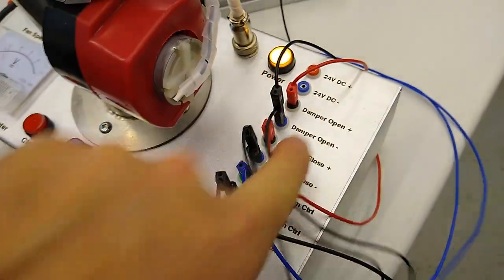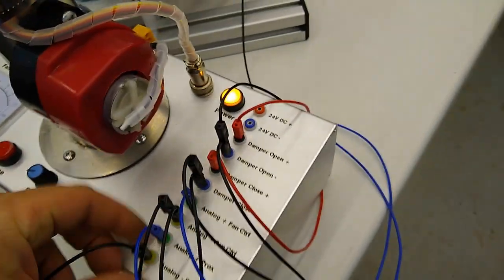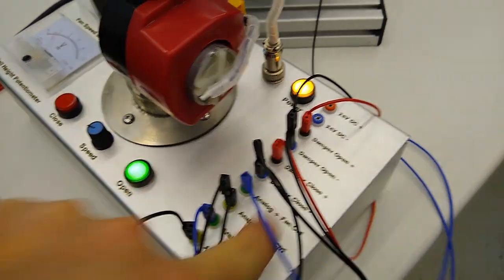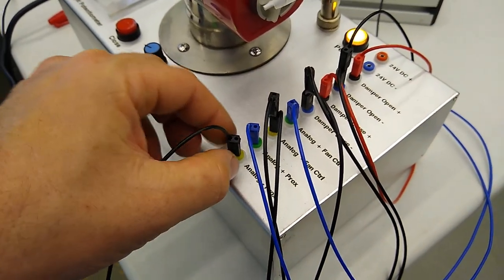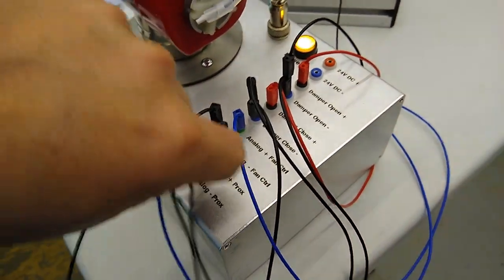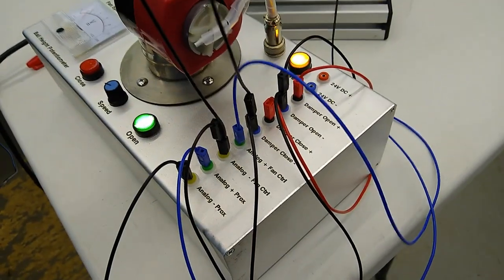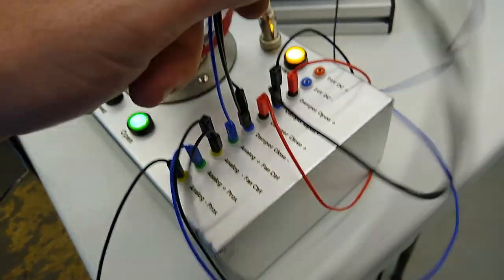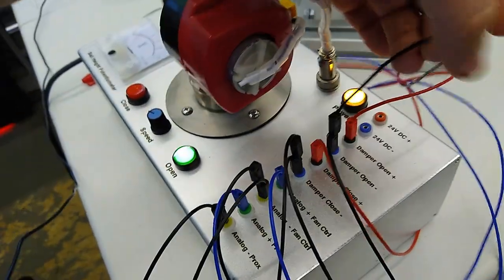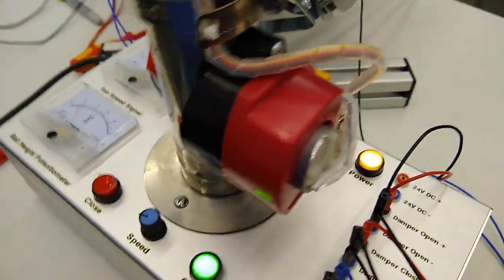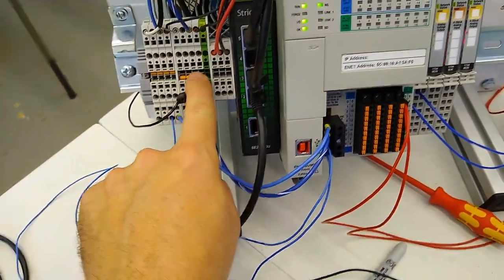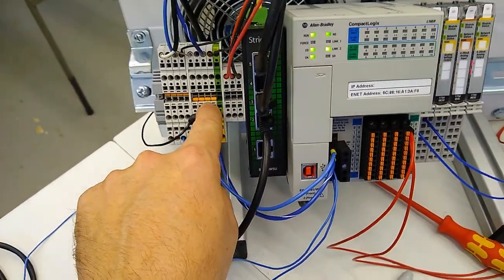So over here is all the wiring to it and really you jumper all of the minuses together. We have our analog prox minus jumpered to our analog fan control minus which is then jumpered to our damper close minus which is then jumpered to our damper open minus and then we have one single wire coming over to our right set of terminals which is our zero volt.